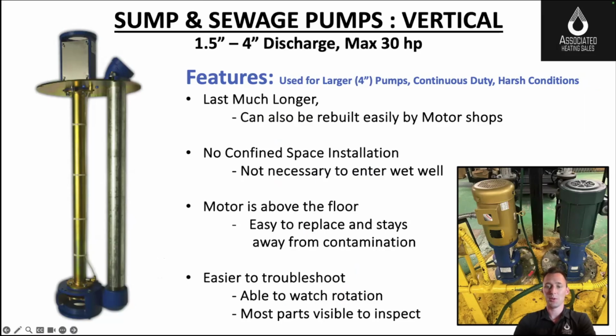The vertical pumps put the motor outside the pit. My cursor here, you'll see the motor's outside the pit. It's in a mechanical room. It has a motor that's coupled to a shaft that runs down to the impeller and pushes the fluid out the discharge pipe. So again, these were very common. They still last a long time. They're a heavy duty pump, and they do really well when we can get the motor out of the pit so the motor doesn't burn up under heat or corrosive environments. We can make the legs and the discharge pipe stainless steel.